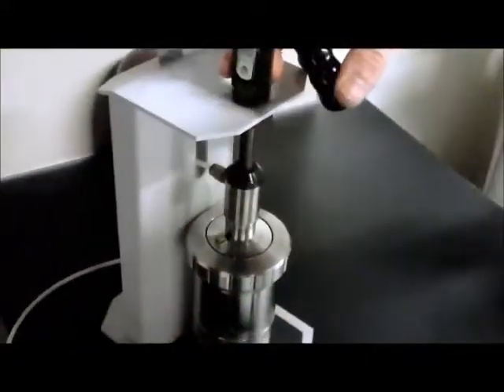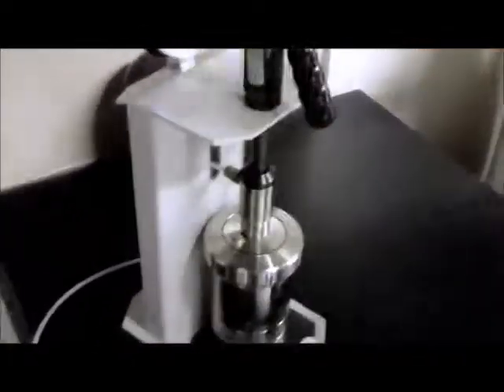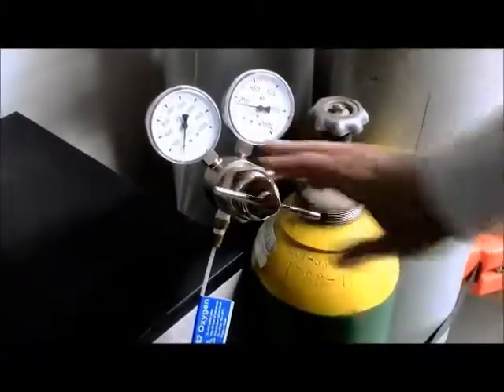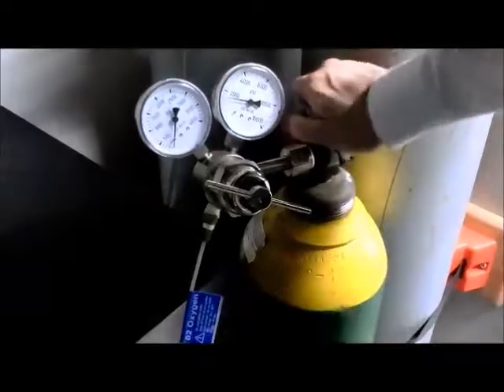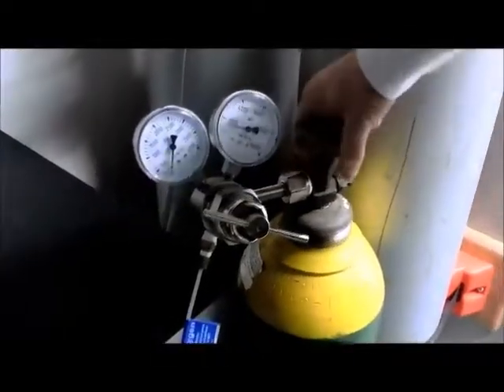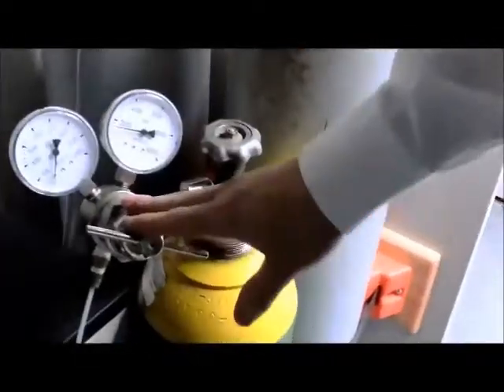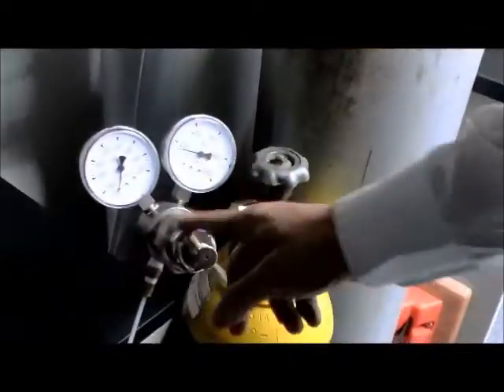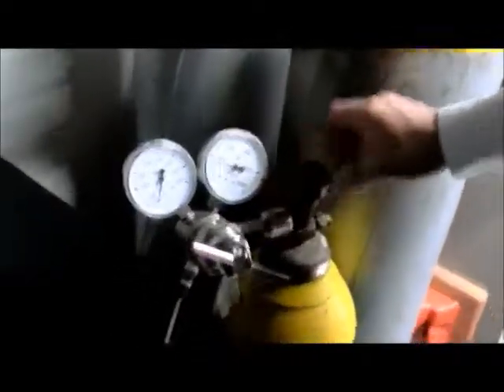Okay. So, filling station, you set the bomb on the marks, and then you lock the bomb down till it clicks. Okay, that's opening the valve? That would open the valve, but we have our tank closed currently. Right. So we make sure that our tank is not going to fill this instantly with oxygen. We turn our regulator valve closed, and then we can open up our gas. So your regulator is now in the off? Our regulator is now in the off. You turn that counterclockwise to turn it off. That's counterintuitive, isn't it? It is counterintuitive. Oh boy, that's not good.